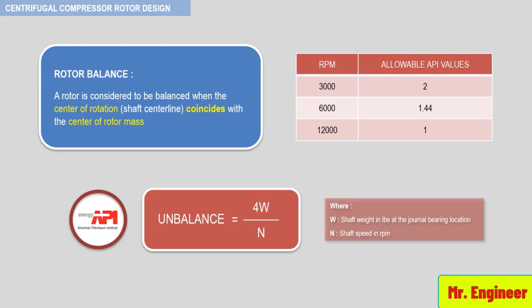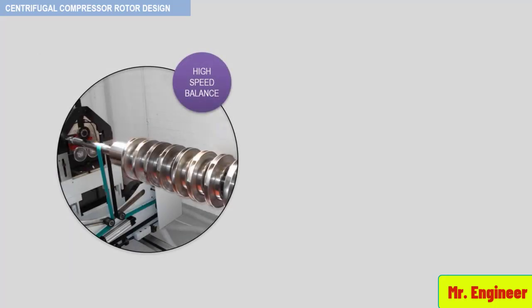Recently, some vendors have eliminated progressive balance and are using high-speed balance. This procedure reduces balance time and cost, but requires that successive rotor balances must always be performed at high speed, since there is no low-speed reference balance. More importantly, the contributing source of rotor imbalance is hard to define, since a progressive balance was not performed.